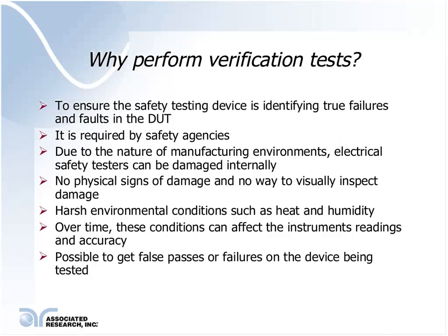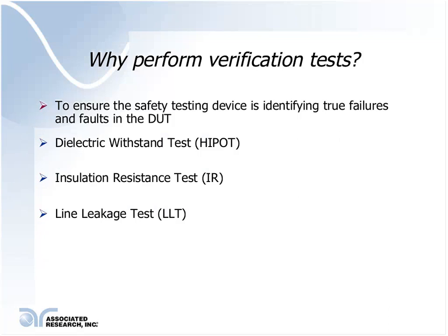Also, environmental conditions like heat and humidity can affect the instrument's readings and accuracy over time, and it is possible to get false passes or failures on the device that is being tested. So this is why safety tester verification is being given so much importance, and rightly so.